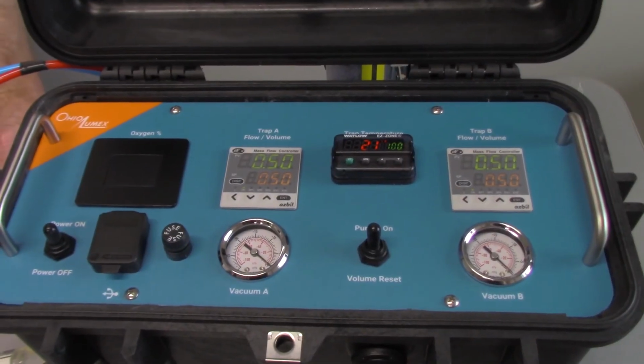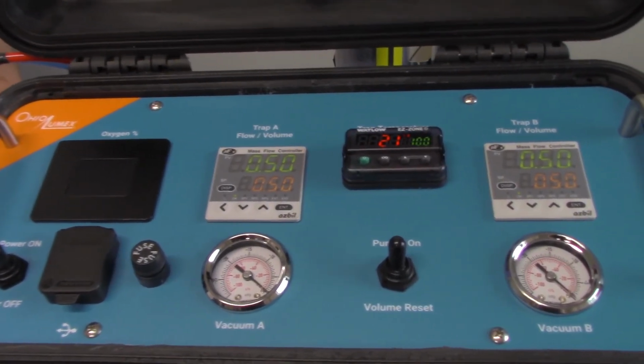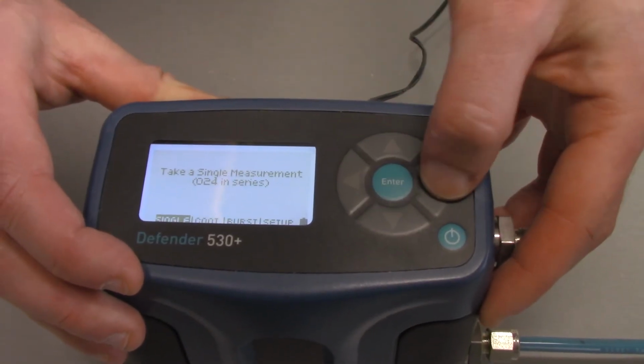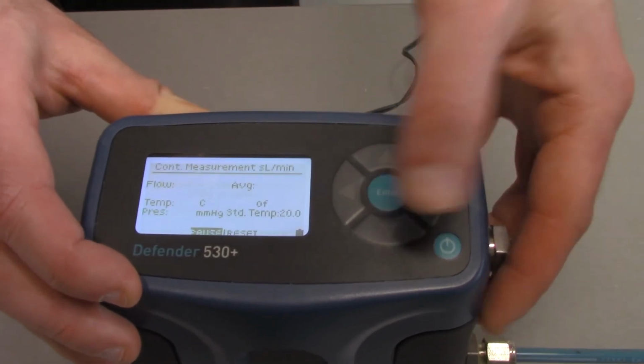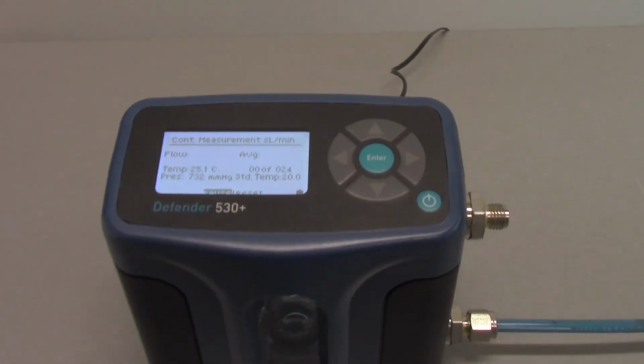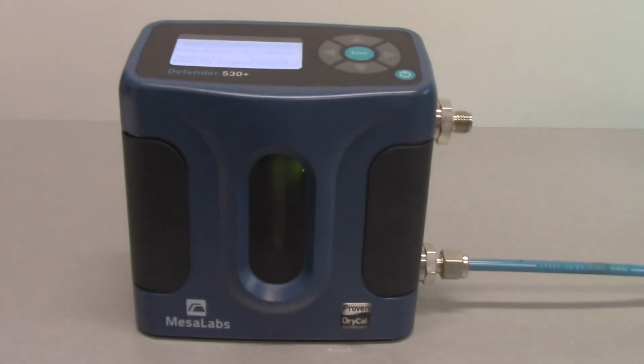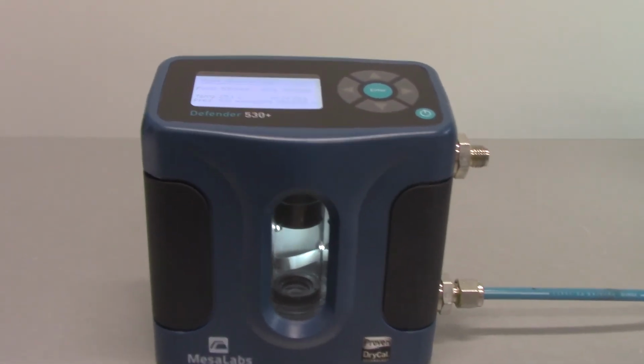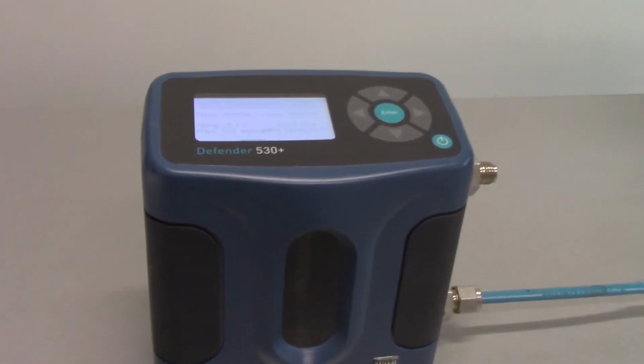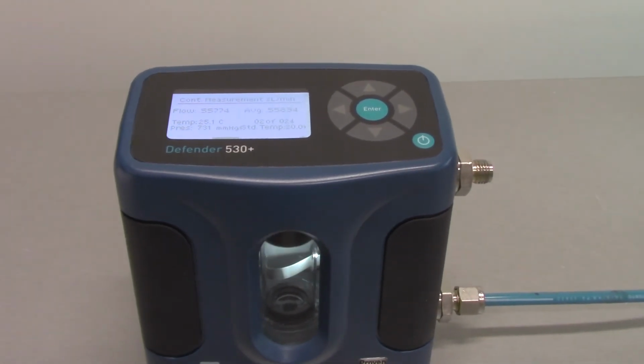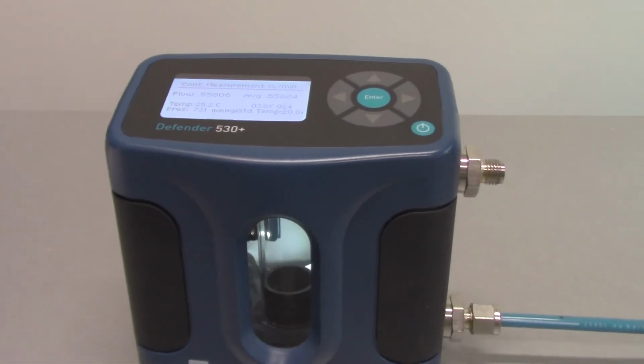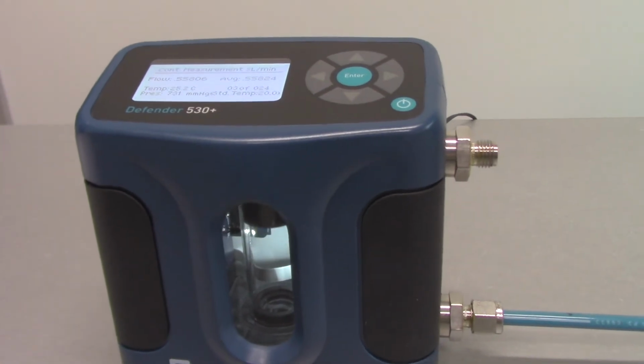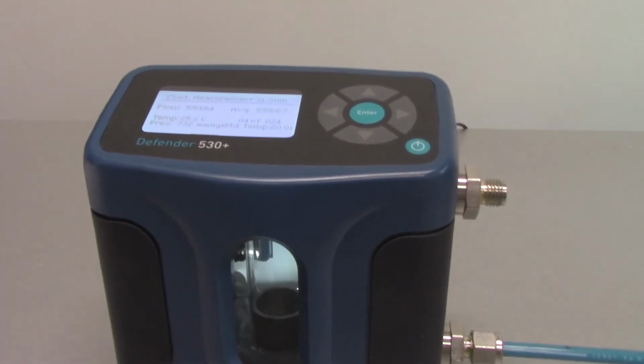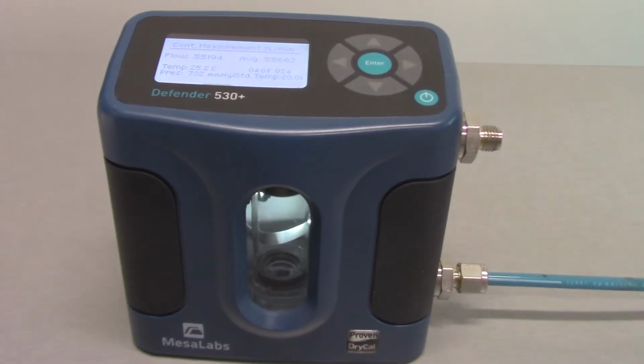The pressure side of the RGFM needs to be hooked up to the exhaust of the sampler while the sampler is pulling actual stack gas at an intermediate flow rate, put into continuous flow measurement mode, and then allowed to stabilize for several minutes. Once the RGFM's internal temperature is stable, you can begin recording RGFM flow rates in order to calculate an average and compare to the selected flow rate. This procedure will need to be done for both sampling trains. Refer to Method 30B and contact Ohio Lumex for more detailed instructions on how to perform this procedure.